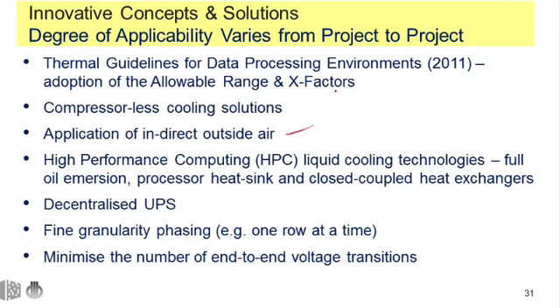We're seeing high performance computing become more prevalent. I wouldn't say it's mainstream at the moment, but Don mentioned earlier loads up to 60 kilowatts per cabinet. That will require a slightly different way of thinking with respect to cooling those type of applications, and there are bleeding edge solutions out there at the moment, including full oil immersion solutions through to processor heat sink cooling solutions to more commercially available close coupled heat exchangers, rear door heat exchangers and such like.